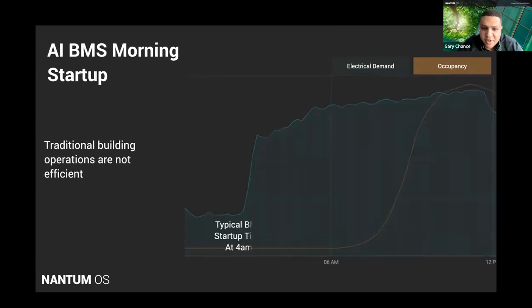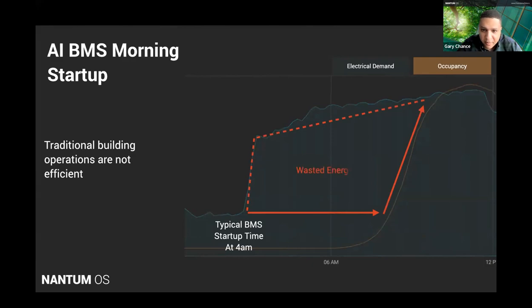This is a look at the traditional building. Most office buildings, large office buildings, teams start up their BMS systems at around 4 a.m. Occupants and electric demand is the green part of the chart, and orange is occupancy. Most buildings start their BMS at 4 a.m. when occupants don't arrive until 8 or 9 a.m. So there's a big opportunity on a daily basis to reduce energy use every single morning.